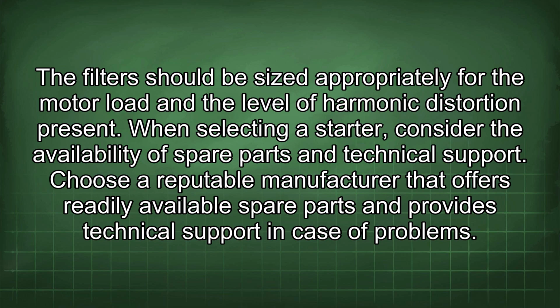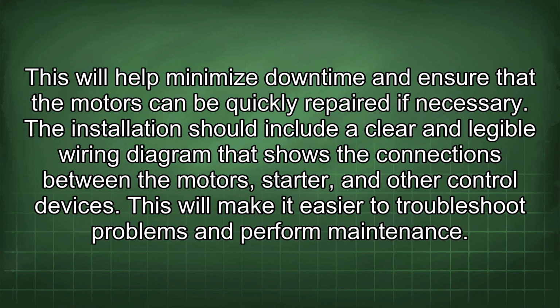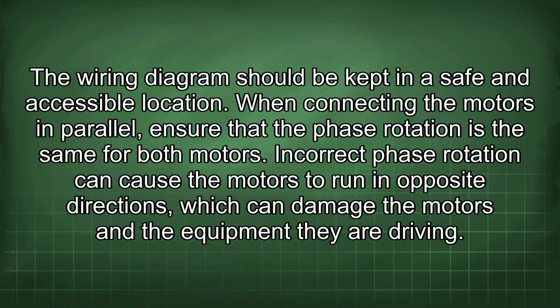When selecting a starter, consider the availability of spare parts and technical support. Choose a reputable manufacturer that offers readily available spare parts and provides technical support in case of problems. This will help minimize downtime and ensure that the motors can be quickly repaired if necessary. The installation should include a clear and legible wiring diagram that shows the connections between the motors, starter, and other control devices. This will make it easier to troubleshoot problems and perform maintenance. The wiring diagram should be kept in a safe and accessible location.